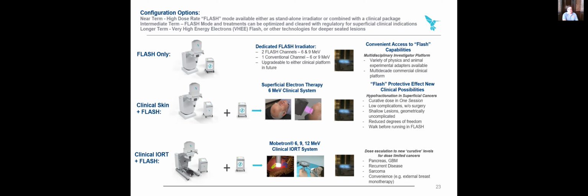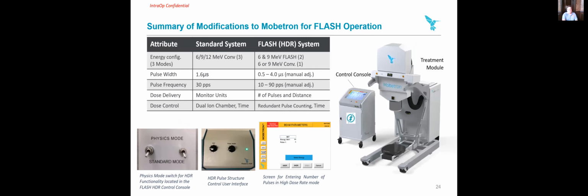But I think in the intermediate term, this kind of platform people can find a way to pay for. They can get their experiments done using an existing clinical platform that's already been verified by the market for 20 years. The modifications we made to this clinical system are in this little flash controller that I keep showing with a little lightning bolt on it. For the standard system in the center column, flash is on the right, 6 and 9, 2 channels for flash, and 1 channel where you choose 6 or 9 for your conventional calibration standard. You can vary that pulse width and you can vary that frequency, and that sets the pulse structure that I showed you a few slides back.